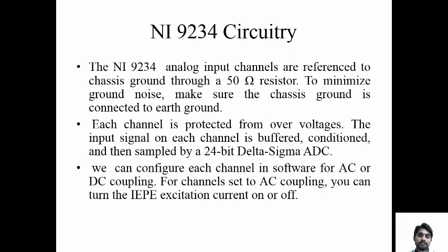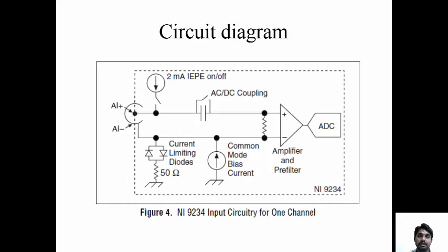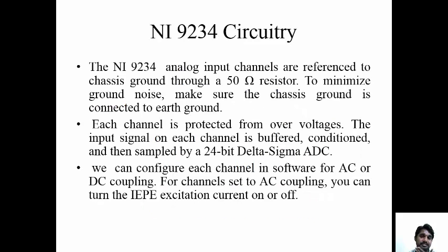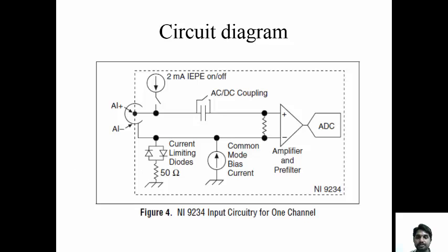The NI9234 circuitry is designed with a 50 ohm resistor connected to ground, and current limiting diodes below that. The advantage of the 50 ohm resistor connected to chassis ground is to minimize ground noise. Analog input channels refer to chassis ground through the 50 ohm resistor by default. Each channel is protected from overvoltages, and the input signal on each channel is buffered, conditioned, and sampled by a 24-bit delta sigma ADC. This converts physical or electrical signals to digital for PC-based applications.